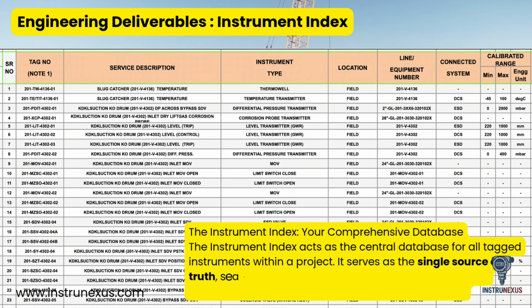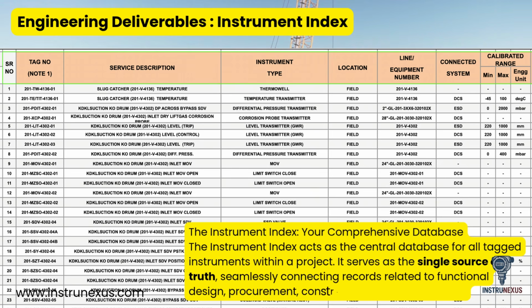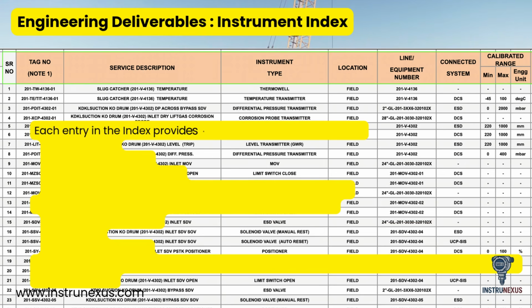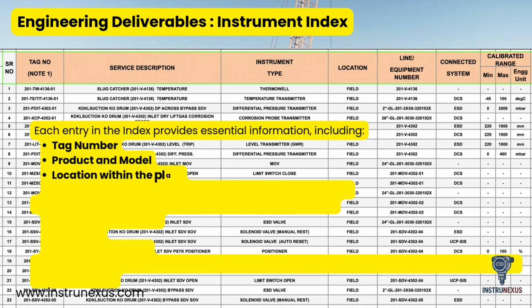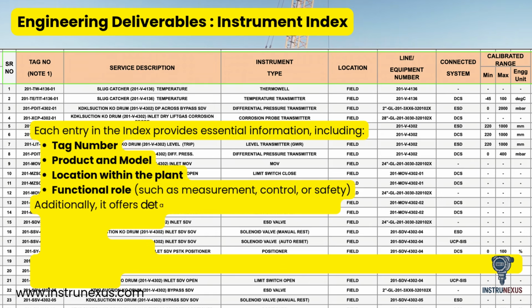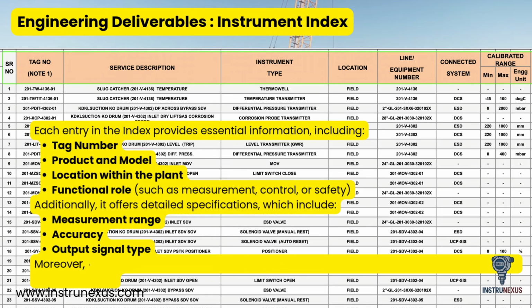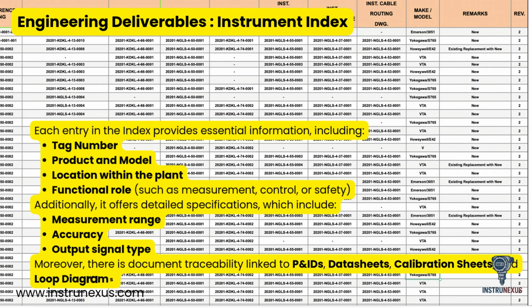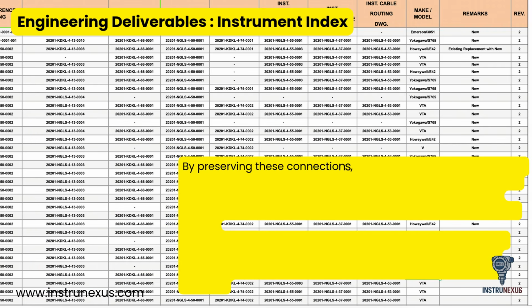It is the single source of truth, linking functional design, procurement, construction, and maintenance records. Each entry in the index contains critical data: the tag number, product and model, its location within the plant, and the functional role it plays, whether for measurement, control, or safety. It also includes detailed specifications, such as measurement range, accuracy, and output signal type, along with document traceability to P&IDs, datasheets, calibration sheets, and loop diagrams. By maintaining these links, the instrument index ensures complete traceability and data integrity.